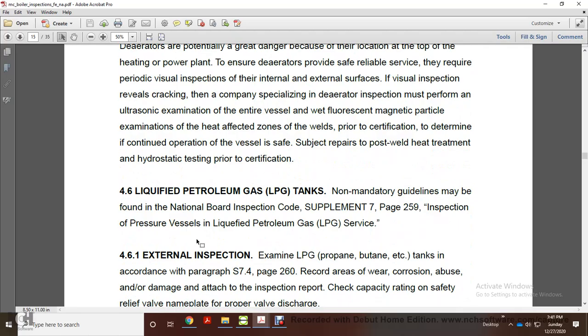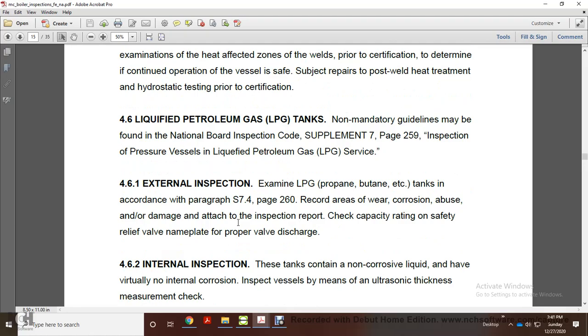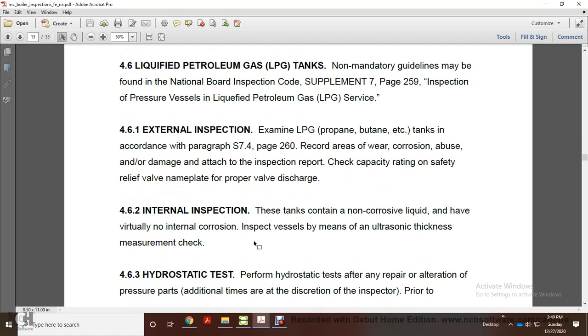4.6 Liquid petroleum gas tanks. Non-mandatory guidelines may be found in the National Board Inspection Code Supplement 7, page 259, Inspection of Pressure Vessels in Liquid Petroleum Gas Service. 4.6.1 External inspection. Examine the liquid petroleum gas, propane, butane, etc. tanks in accordance with subparagraph S7-4, page 260. Record areas of wear, corrosion, abuse, and damage, and attach them to the inspection report. Check the capacity rating on the safety relief valve nameplate for a proper valve discharge.